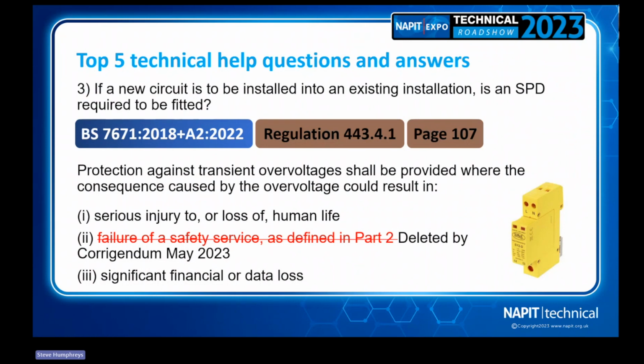Now, there's an interesting conversation in the industry at the moment about SPDs. We've recently done a podcast with Surge, which talked about their use. We used to fit these a lot back in the day in IT buildings where significant data loss was a massive issue, so they would always have surge protection in. But these days, in reality, even in domestic settings, SPDs are a sensible option. You can now buy a consumer unit that comes preloaded with a surge protection device, a Type 2. It's not that expensive, but you are protecting a lot of expensive electronic equipment in the home.